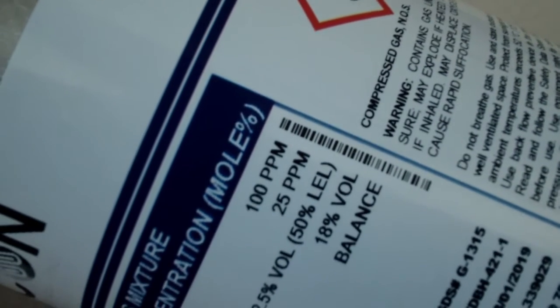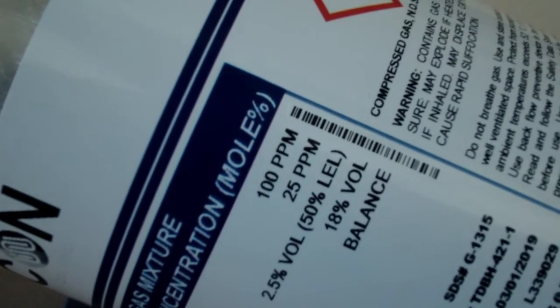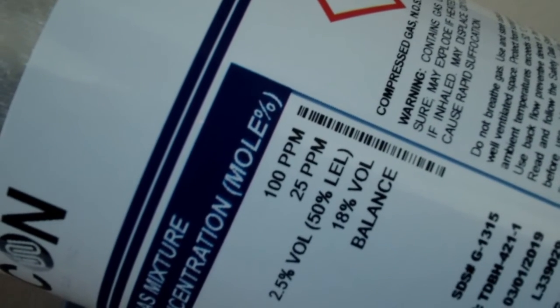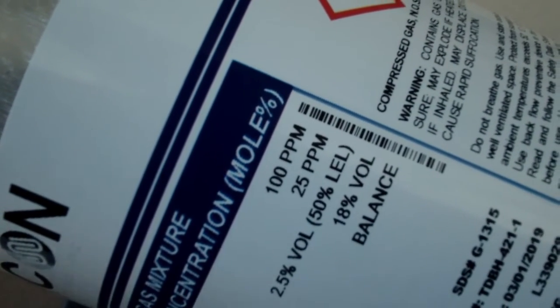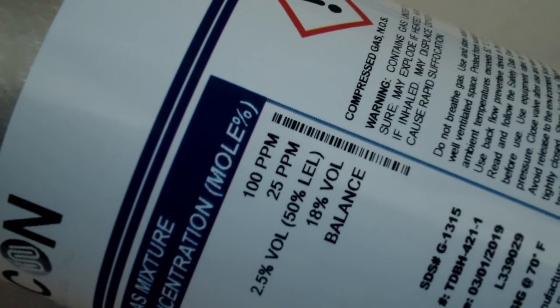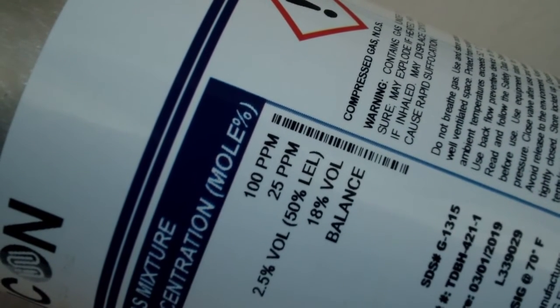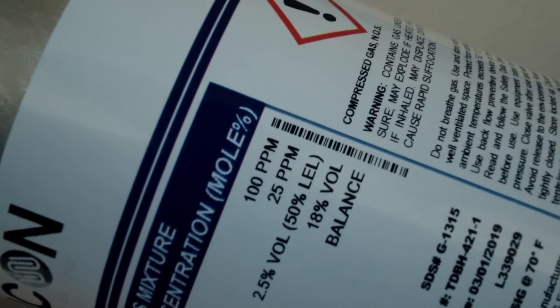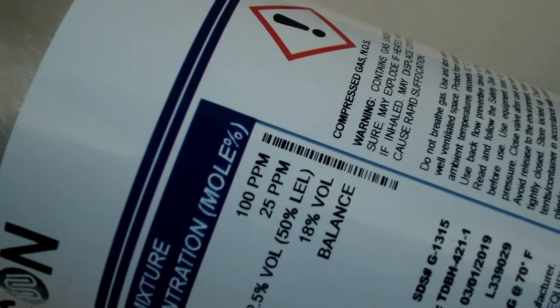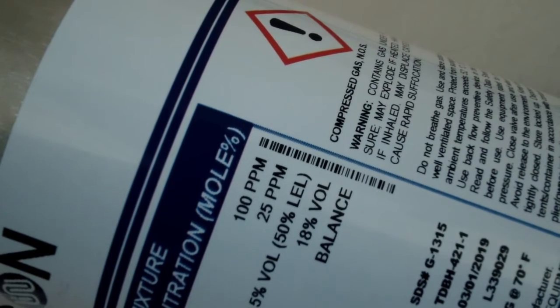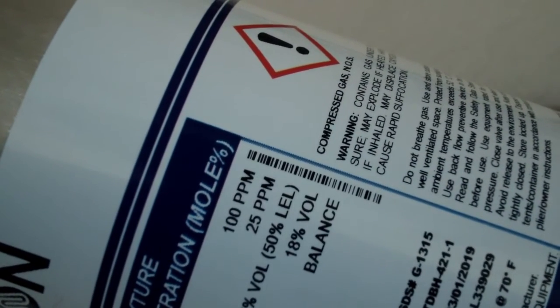The Cal gas that's sent to us is, I'm just leaning the bottle over there. I hope you can read that. It's a 4-gas combined gas. It has 100 parts per million of carbon monoxide, 25 parts per million of hydrogen sulfide. It uses methane as the flammable gas, and it's at 50%. 18% volume on O2, and the balance is nitrogen. So basically, when I plug this into the meter, that's what I want my meter to show me to let me know that it is operating properly.